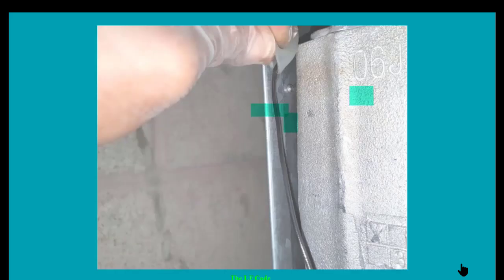So another tip regarding the LF code is the electrode lead itself. So what we've got here, you could get a breakdown on the lead. So if you look carefully at the top, you can see a bit of wire. So the actual insulation of the black cable, the sheathing, is breaking down. So you need to inspect that lead, see if there's any breaking down. If you can see any wire, that means that could be causing the problem as well. So inspect that cable all the way through and make sure there's no breaking down.